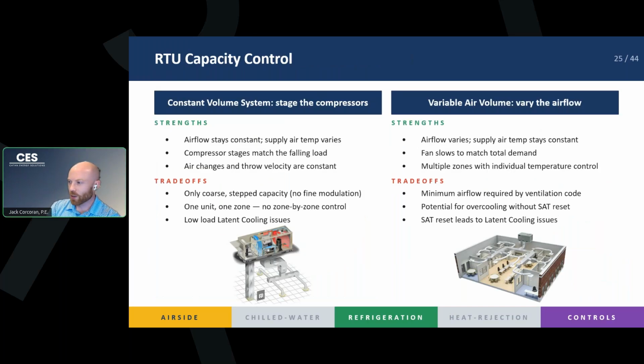Now, how do these control capacity, right? We talked about our VAV systems, our variable air volume, and our constant volume systems. These are the two main control paths that we use in our rooftop units. You can imagine that, in order to control capacity, we can either vary the airflow, right? If we send more cold air to a space or less cold air to a space, we're going to change the temperature of it. Or we just send hotter air or colder air to the space in order to change the temperature. And that's what these two systems are.